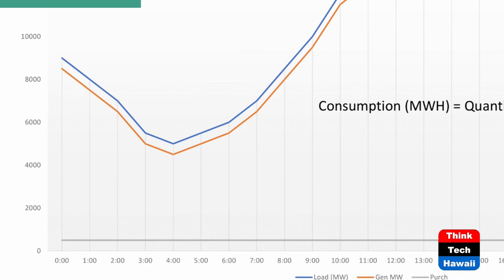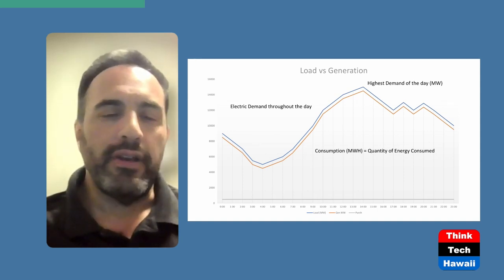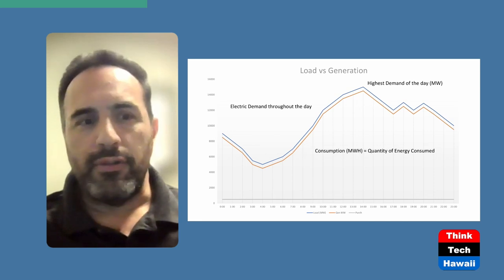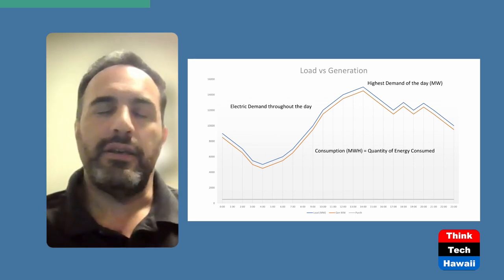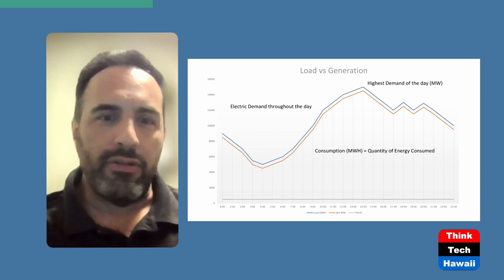Everything in the area under those curves is an integrated value — any point on that curve times the time elapsed. That is what gets billed, measured, or metered, and that's the utility revenue counted as megawatt hours or kilowatt hours produced. This is often where confusion arises with nameplate ratings. If a power plant can produce 100 megawatts nameplate — that is its capacity, it cannot make more than that. If it ran for 24 hours, we say we made 2,400 megawatt hours. That sounds like a lot more than it is — in reality it can only produce 100 megawatts at any given point in time.